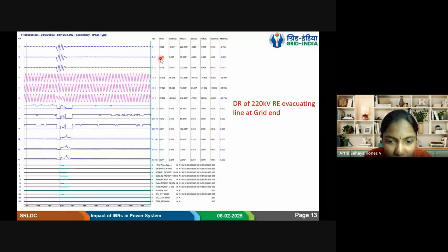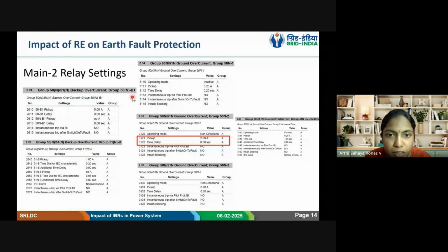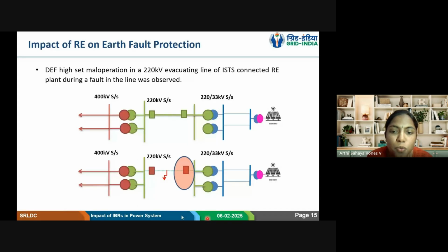So in the grid connected station, there is only pickup, whereas the RE connected station gave trip. Later we came to know that they had enabled this high set component without any delay. Because of that, this particular maloperation had happened. So this is one impact. Now we are talking about the fault in the grid and the impact on the 220 kV RE connected evacuating line protection. Similar thing also happened when there was a fault in the evacuating line itself.